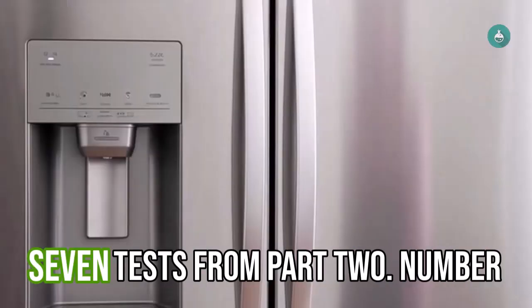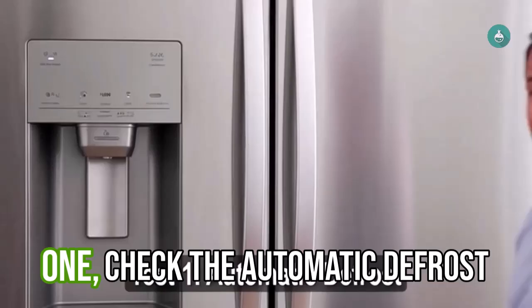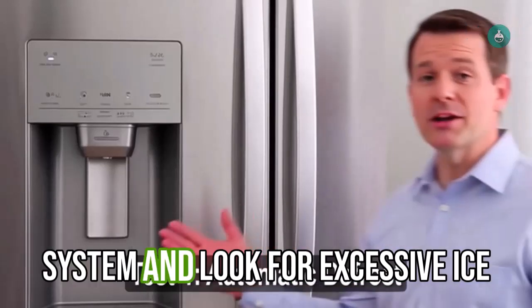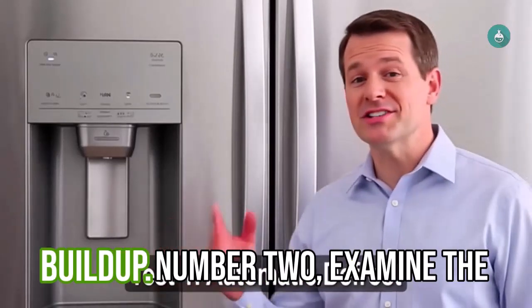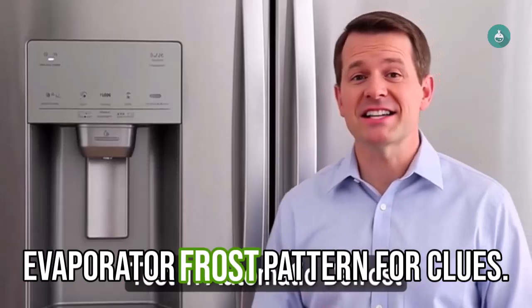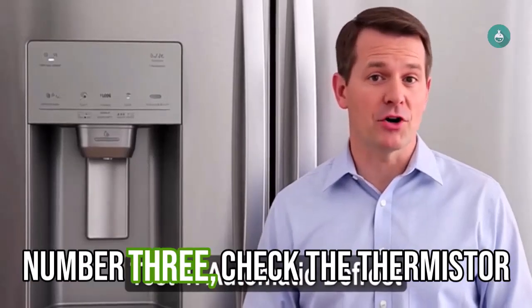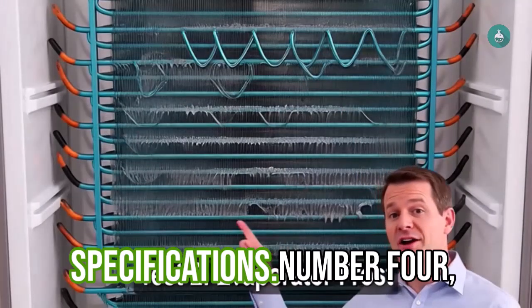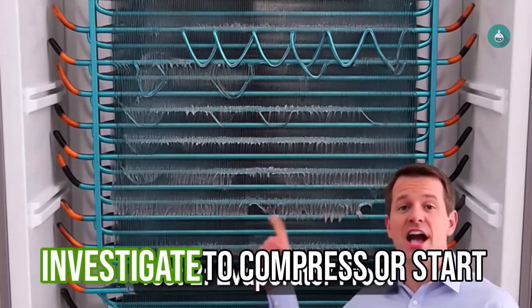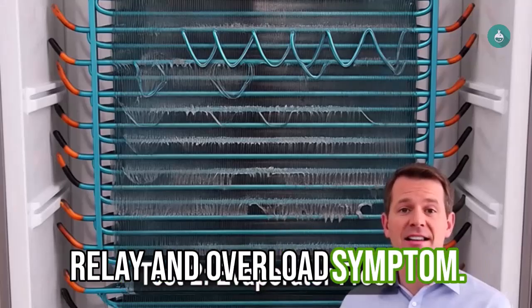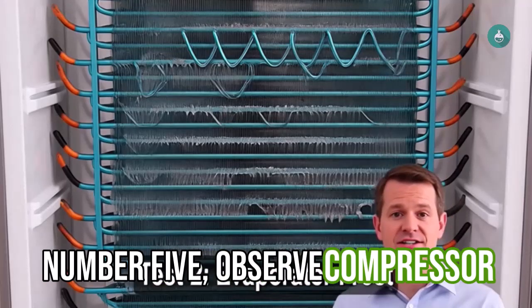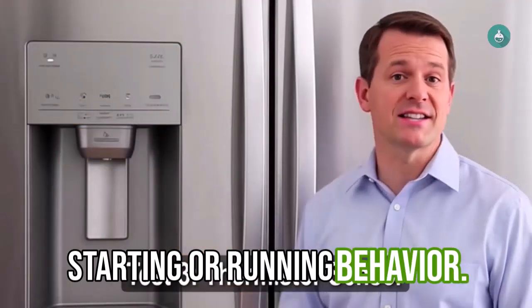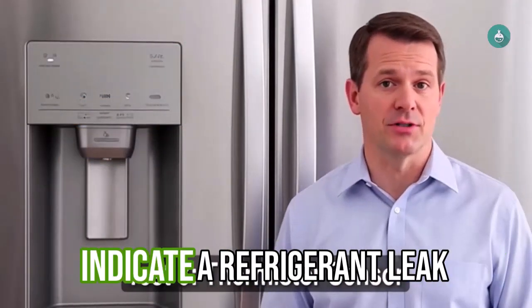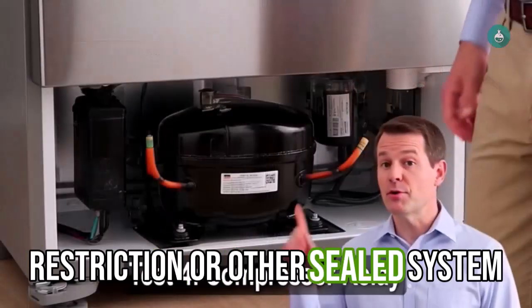Let's quickly review the 7 tests from Part 2. Number 1, check the automatic defrost system and look for excessive ice buildup. Number 2, examine the evaporator frost pattern for clues. Number 3, check the thermistor or temperature sensor according to the manufacturer's specifications. Number 4, investigate the compressor start relay and overload symptoms. Number 5, observe compressor operation and look for unusual starting or running behavior. Number 6, look for signs that may indicate a refrigerant leak, restriction, or other sealed system problem.